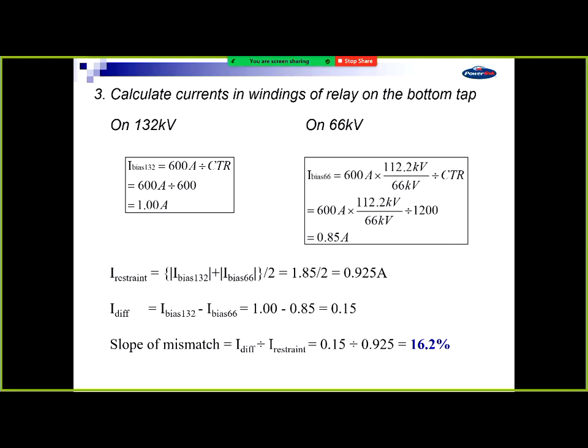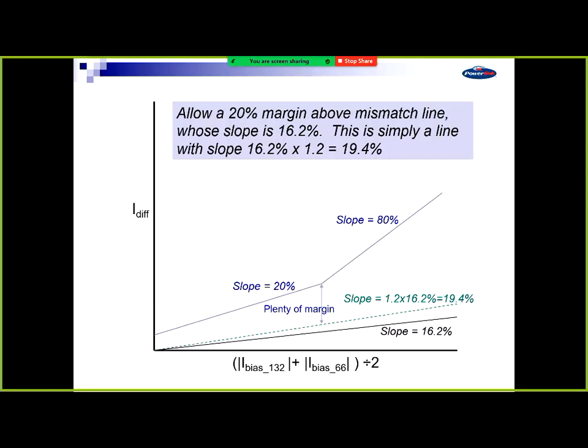So 0.15 amps difference between the HV and LV secondary current is just the tap changer. So you don't want to trip on that. So you get your diff divided by your restraint and you end up with 16.2%. So that's the slope that we want, 16.2. We put a margin of 20% on that, we end up with 19.4. This manufacturer recommends a slope of 20%, so we use 20%, and they say for the second slope, use 80%. So that's how we get above that.